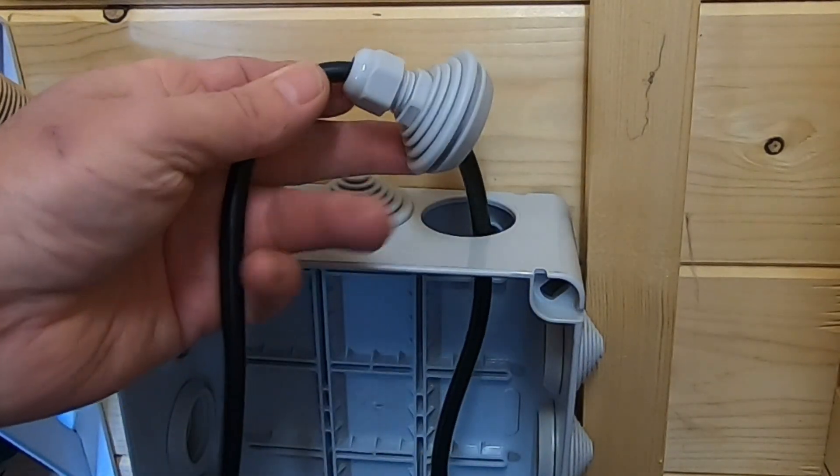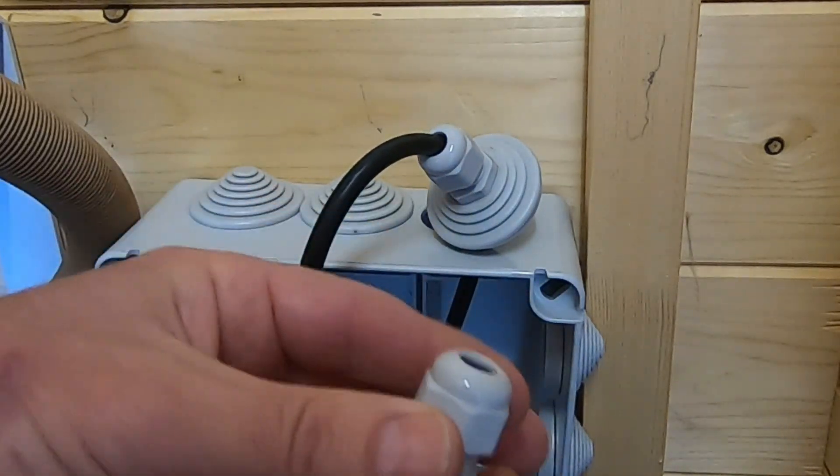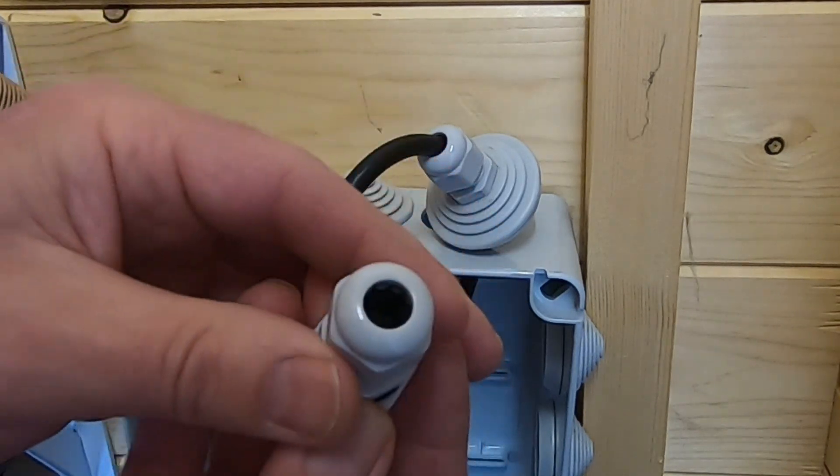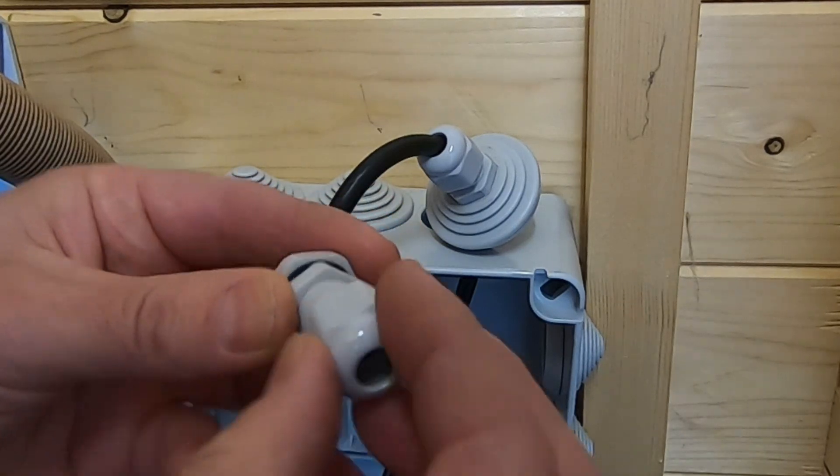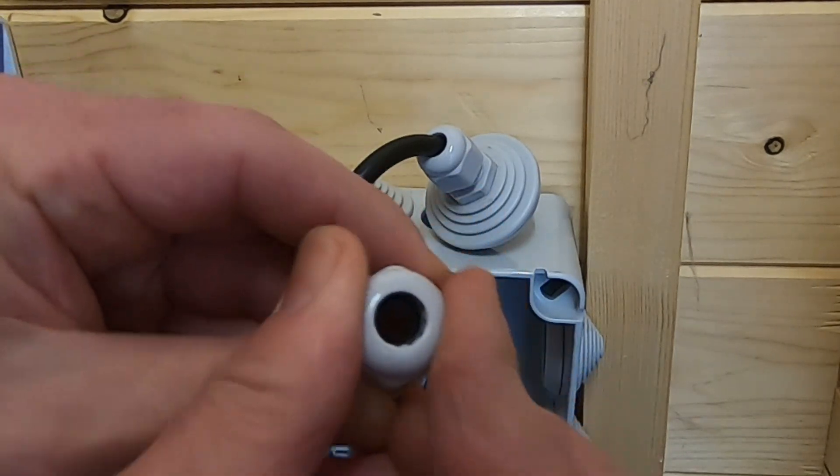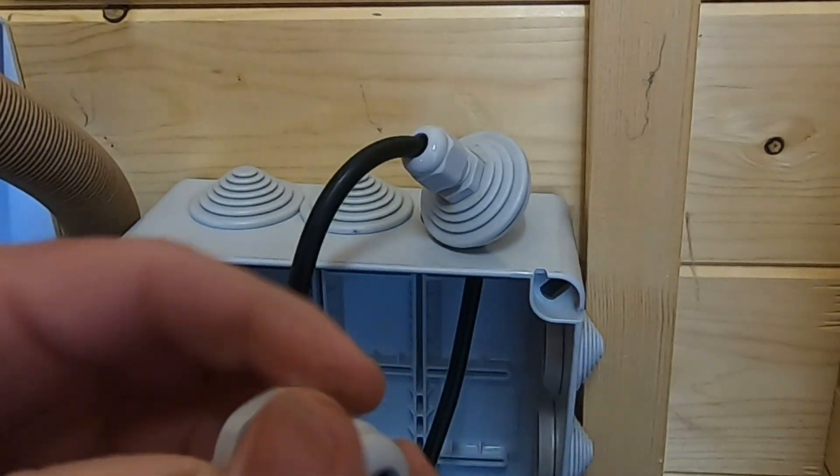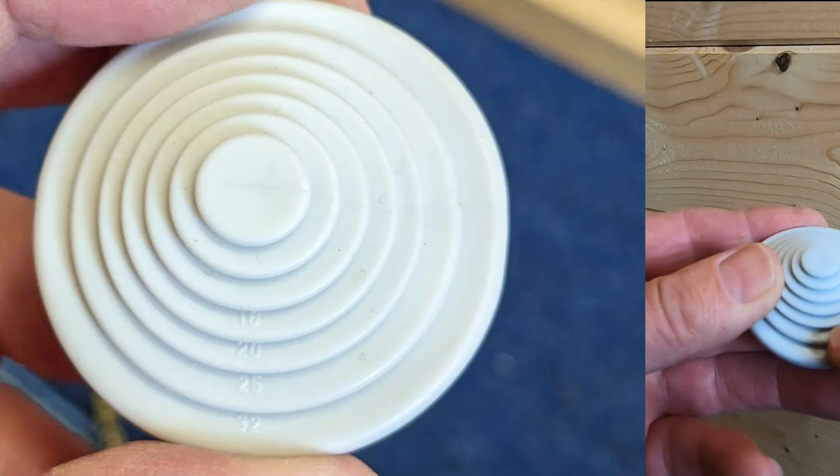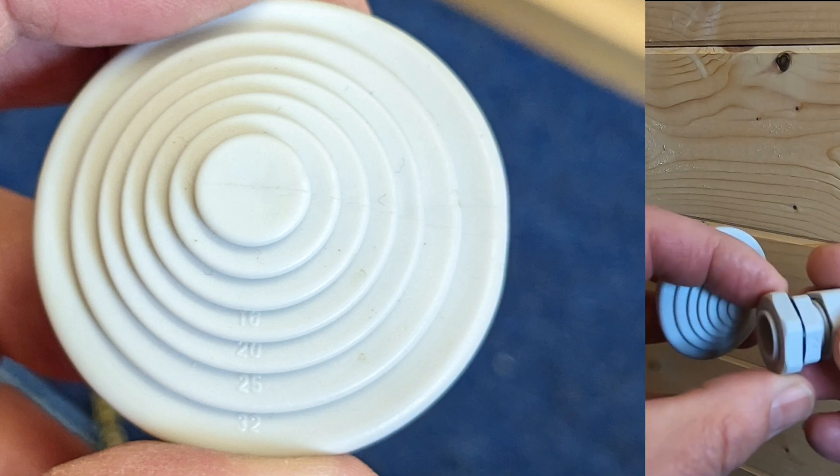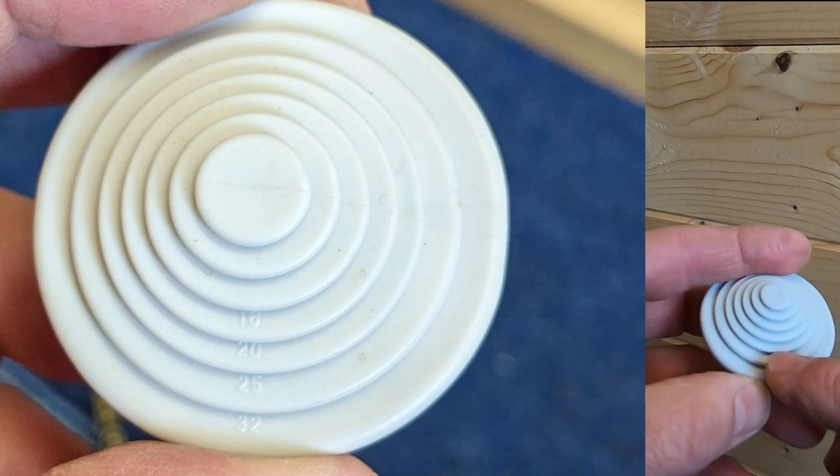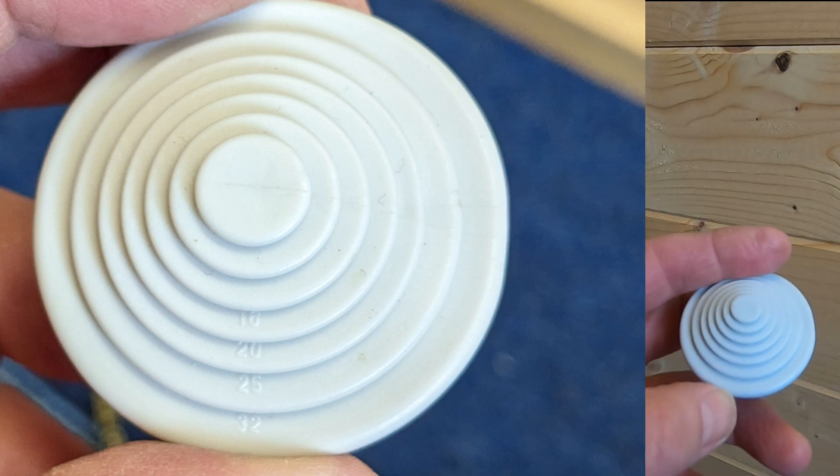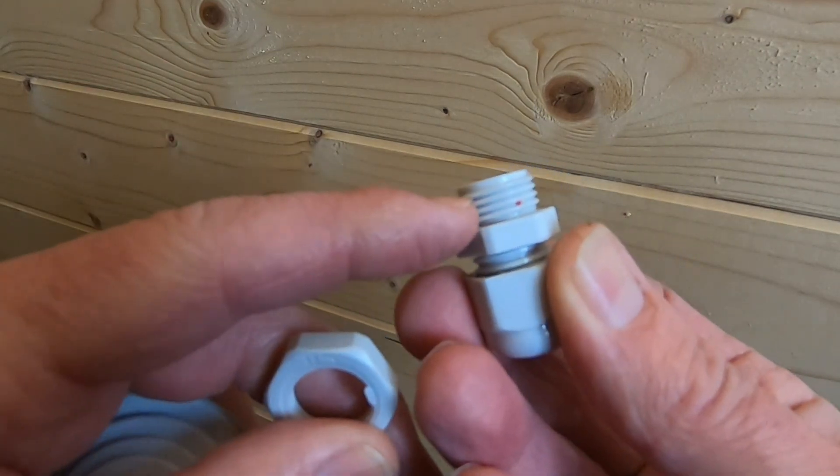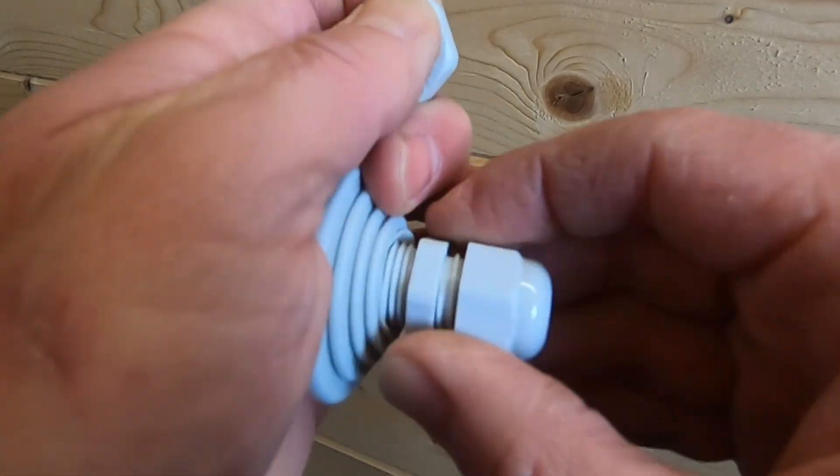I've used a compression gland. If you've ever seen one of these before, put your cable through there, through the hole there. This is a little bit of rubber just there. As you screw this on, screw this down, that squeezes that rubber and it grips the cable. On these grommets you can see that there's some numbers here. The compression gland that goes in here is an M16, so the corresponding number is where you need to cut off. There's not a lot of thread on the gland, so when you push it through like so you see there's not much on there.